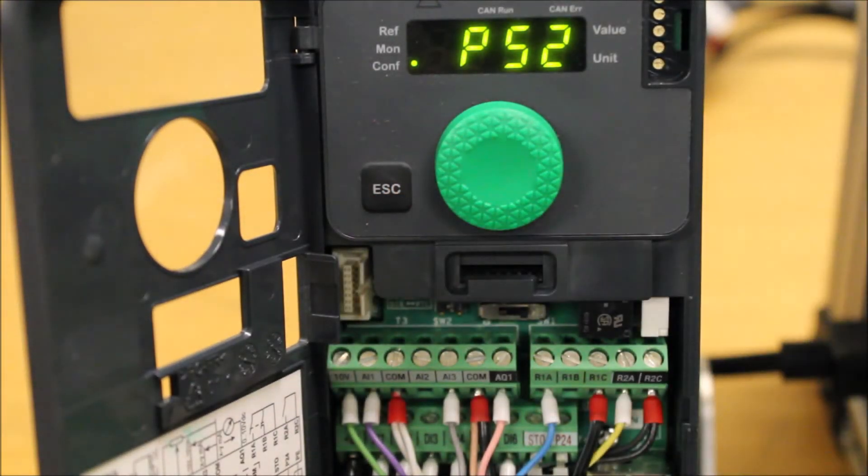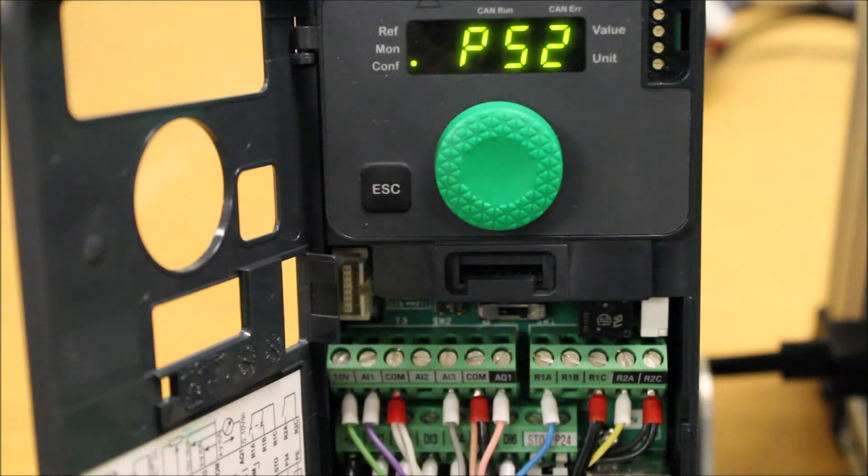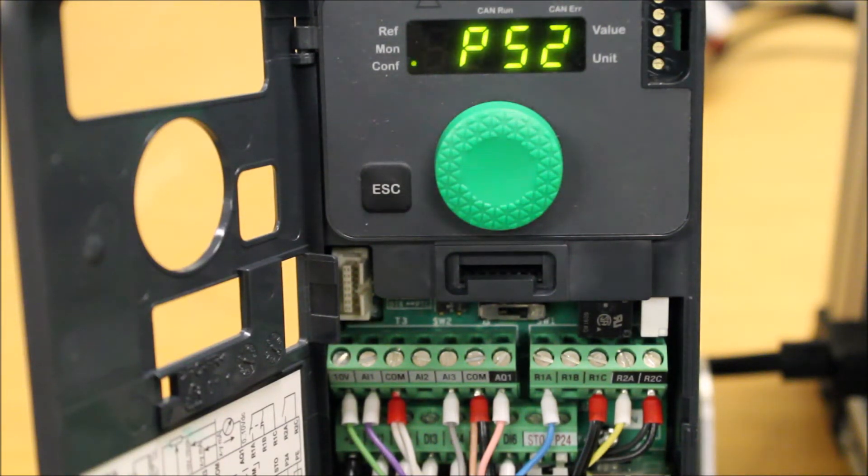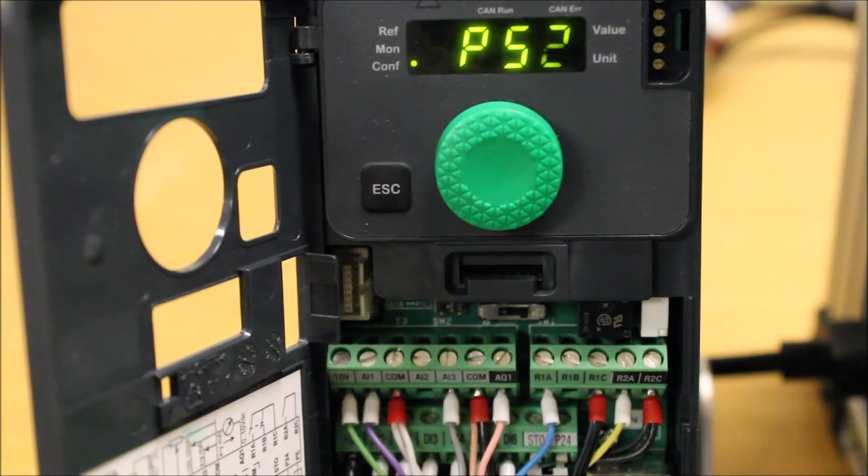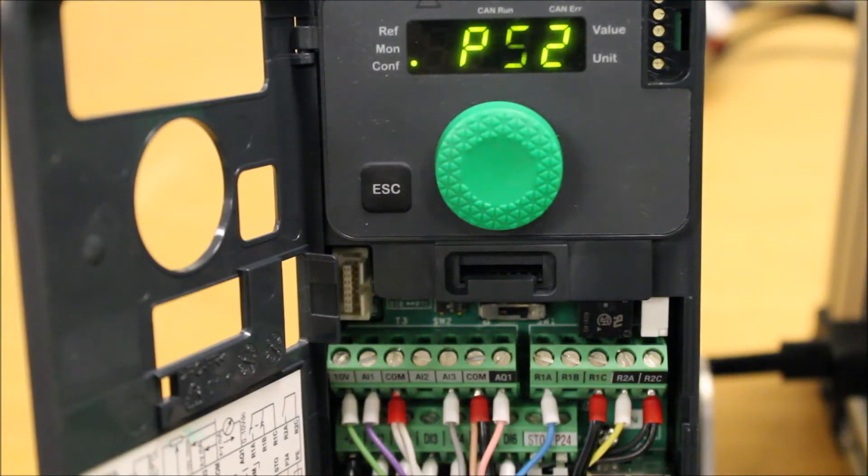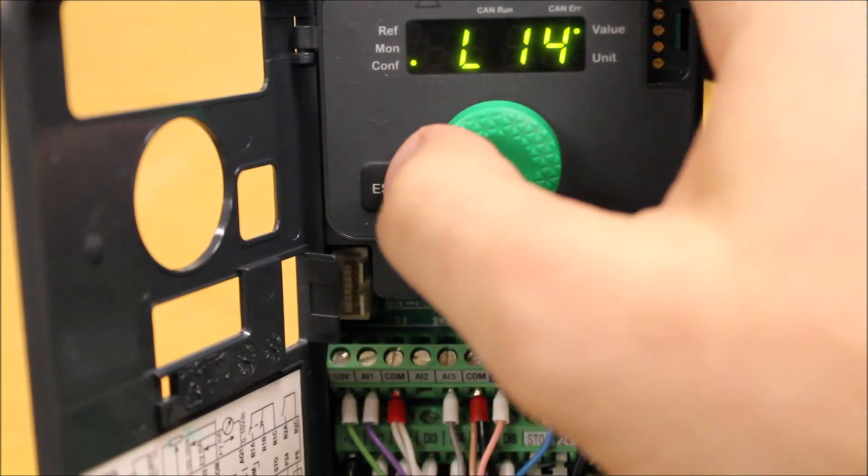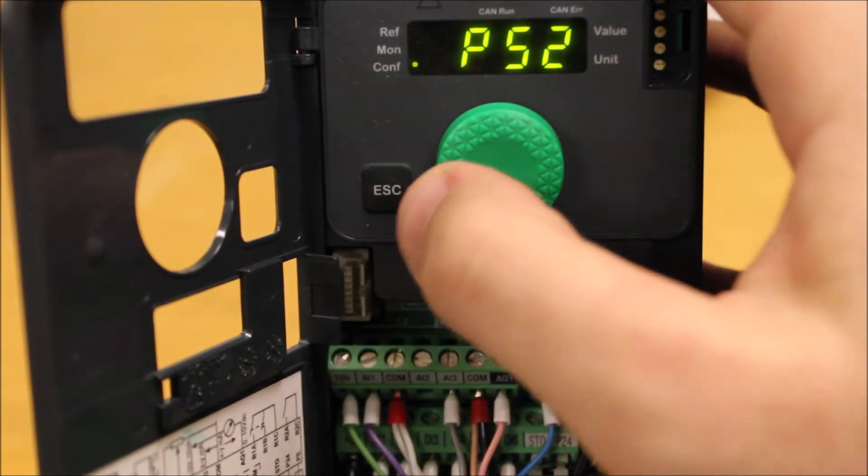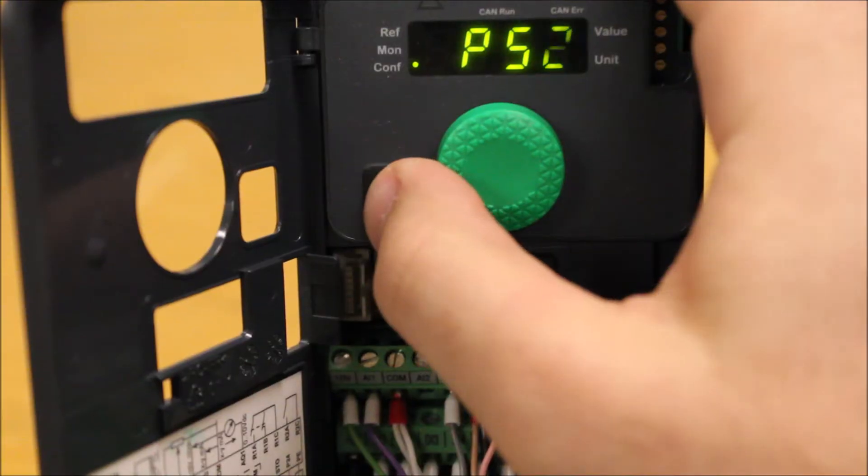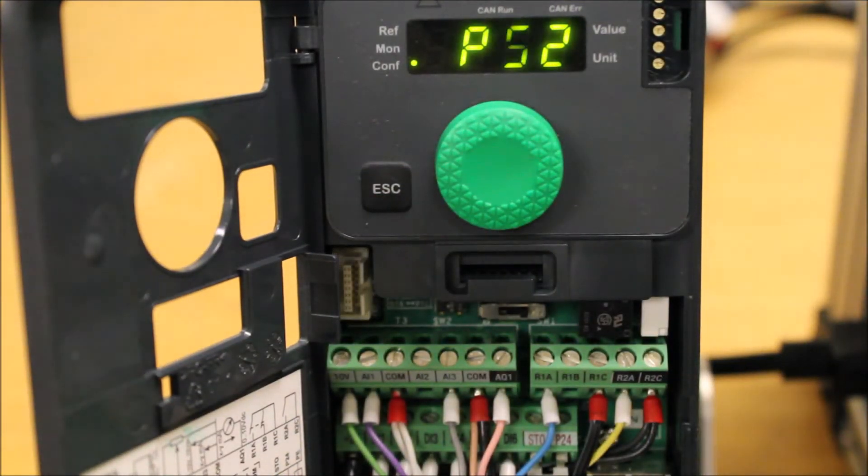What we're going to do is program your first preset as 30 hertz, and the second preset as 60 hertz. And we're going to go one step further and say, if we have both LI3 and LI4 programmed or assigned and turned on, then we're going to go to 45 hertz, just to give you another example.